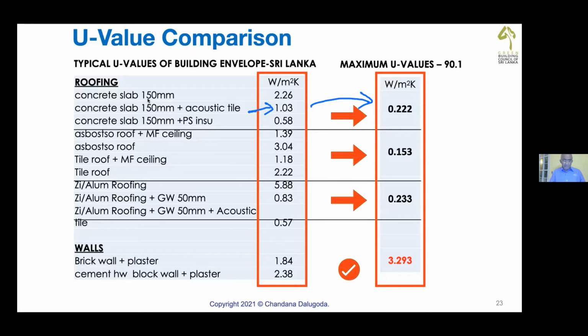Concrete slab with polystyrene insulation is 0.58, that is quite good, but still you have to drop it. Can you see? So you need more thermal insulation. Asbestos roof with mineral fiber ceiling is 1.39, but our target is 0.153. Zinc alum roofing without anything is 5.88, a disaster. Now, zinc alum roofing with 50 millimeter glass wool, that is the Sri Lankan specification we do everywhere, gives 0.83 watt per square meter Kelvin. Very good compared to other structures, but you'll have to further reduce it to 0.2.